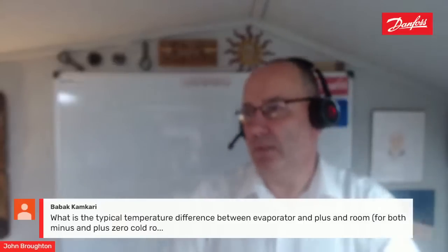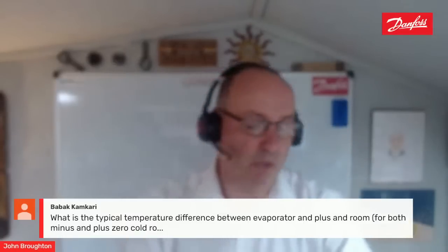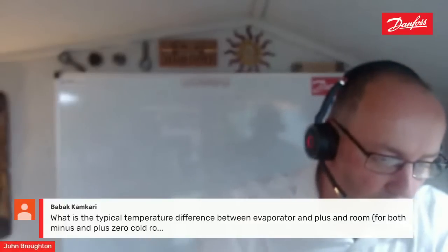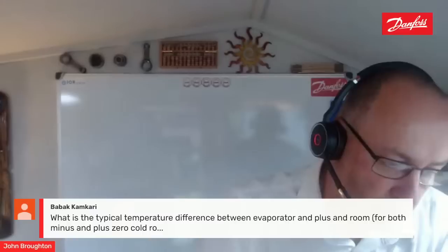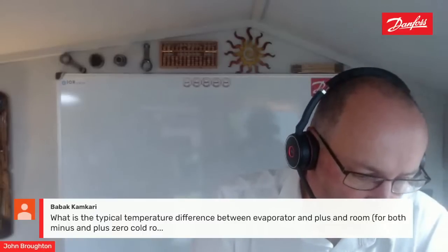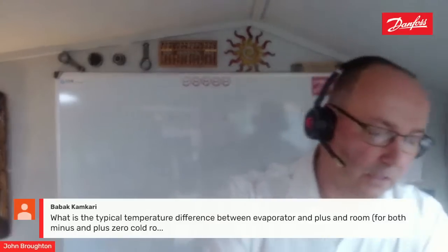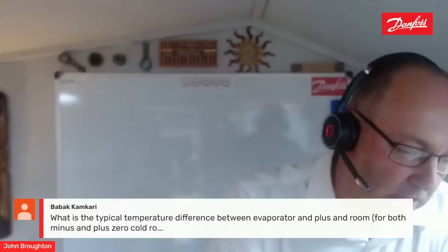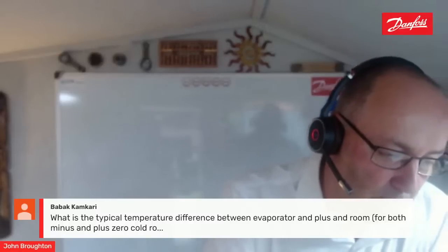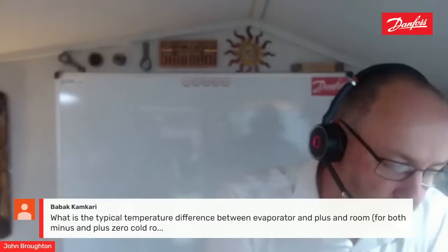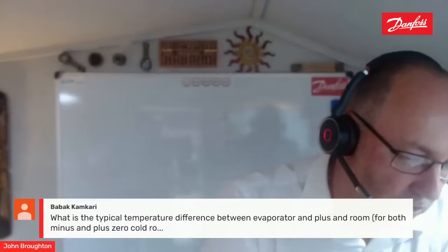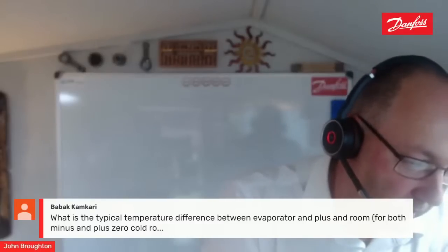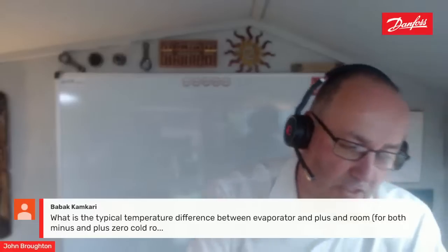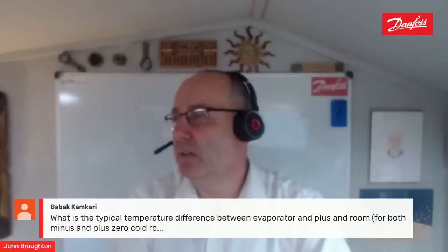Generally, if it's a frozen room, humidity doesn't matter, as a general statement. For temperatures freezing and below, generally a 6K delta T is absolutely fine. And if we're talking about 6K delta T, then let me read my book correctly, because I always have to check this, you're looking at around 80%, 85% humidity.